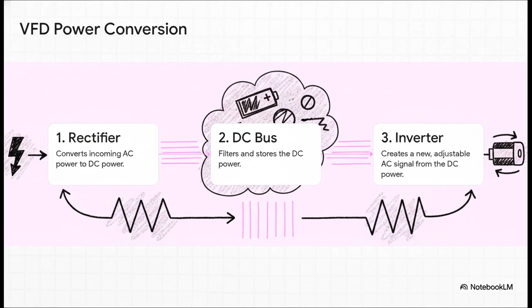And this lays out that internal process beautifully. The first stage, the rectifier, that's what turns the messy AC into clean DC. The second stage, the DC bus, it's kind of like a holding tank that filters and stores that power. And then the final stage, the inverter. Well, that's the artist. It precisely chops up that DC power to build a brand new variable AC wave. It's this AC to DC to AC conversion that gives the VFD its amazing control. So let's just boil this all down to one single slide. If you take away only one thing from this explainer, this is it.